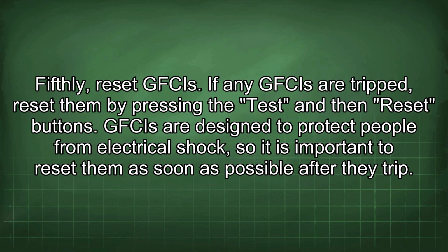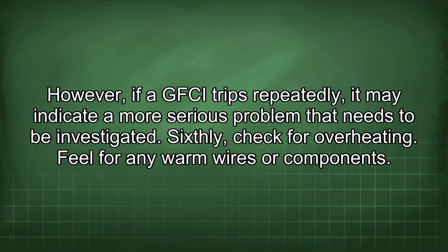Fifthly, reset GFCIs. If any GFCIs are tripped, reset them by pressing the test and then reset buttons. GFCIs are designed to protect people from electrical shock, so it is important to reset them as soon as possible after they trip. However, if a GFCI trips repeatedly, it may indicate a more serious problem that needs to be investigated. Sixthly, check for overheating.